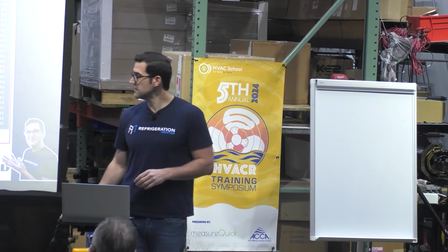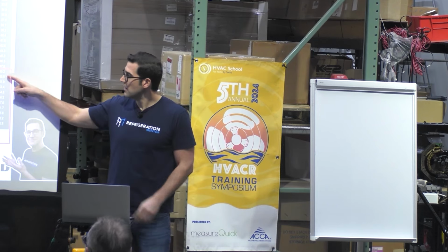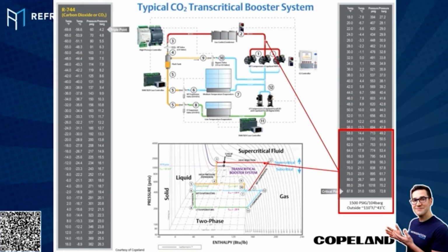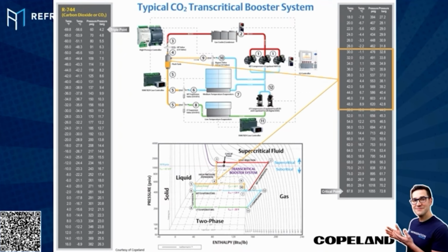Next, this is the pressure range. You could go all the way from 700 psi to 1500 psi on the high side. Okay, so there's a big range, depending on where you're at, what the ambient is out. So you got to consider that. Then from there, we got our flash tank pressure, our liquid pressure. So you guys call this your liquid pressure. So it's the same here. This is the liquid pressure, but it has a range. So you go from 470 all the way up to 620 psi.